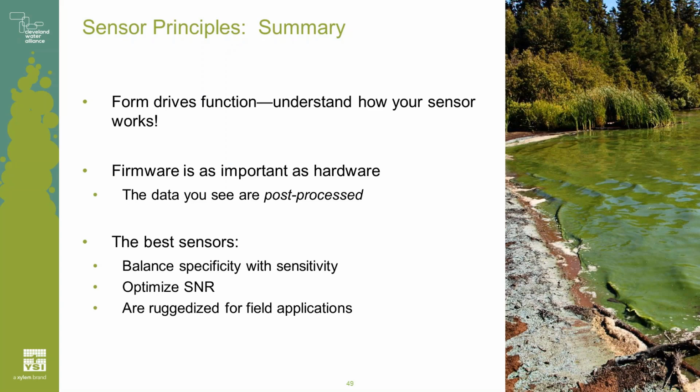So the bottom line is this: as you guys have seen, light passes out of the sensor into the water, and then something has to come back into the detector. If there's a lot of stuff in the water, it's going to interfere with how that light acts. Some of that stuff can give you an artificial fluorescent signal. Some of that stuff can just reflect light back into the sensor, giving you an artificially positive signal.